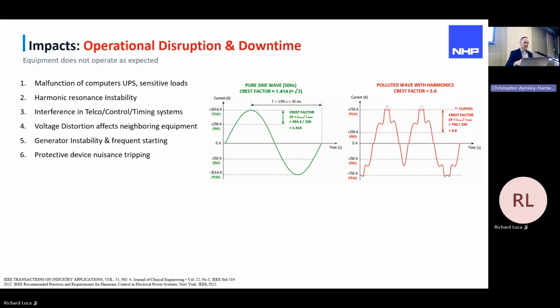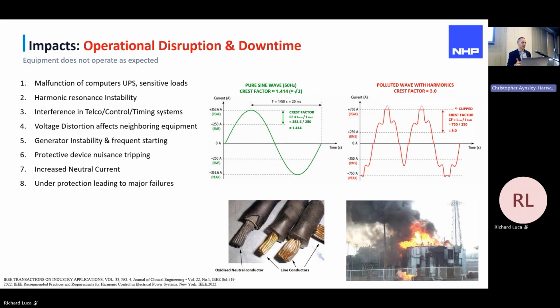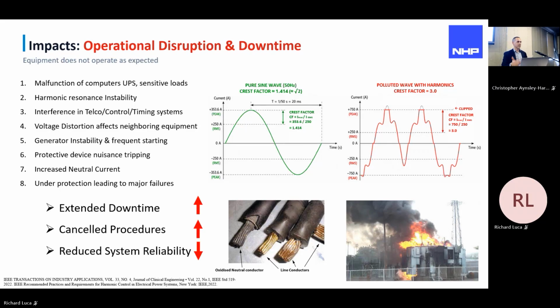But under the standards, there's a standard 60947 part 2, which is the moulded-case circuit breaker standard. And there's a section there where the circuit breakers are tested to a particular harmonic waveform. It's roughly a crest factor of about 2.2, with overall THD roughly 50 to 60%. But if you get a really high crest factor, then that electronic circuit breaker is just seeing a reduced waveform, not the actual true peak, because of the clipping of the internal CTs. We get saturation. And that's no good because it could lead to more catastrophic events. Increased neutral currents. So there's extended downtime here, cancelled procedures, and overall reduced system reliability.